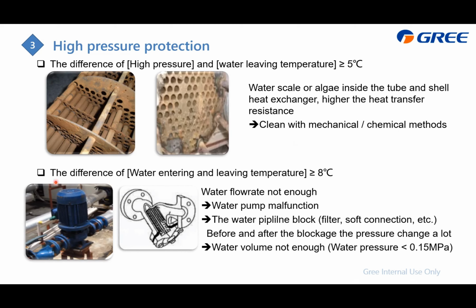And also you can check the difference between the water leaving and entering temperature. The difference should be less than 8 degrees. If higher than that, that means the water flow rate is not enough. And why is it not enough? You can check the water pump, maybe it's malfunctioning, or maybe the water pipeline is blocked, and just focus on the filter and the soft connection. Maybe it's not that good, especially if the water pressure before and after the blockage changes a lot, or maybe the water volume is not enough. At that time, also check the water pressure. If it is less than this value, that means there is not enough water inside.